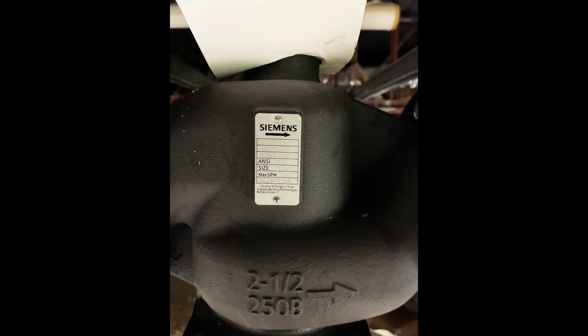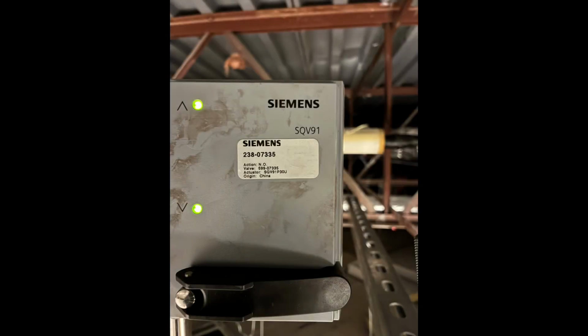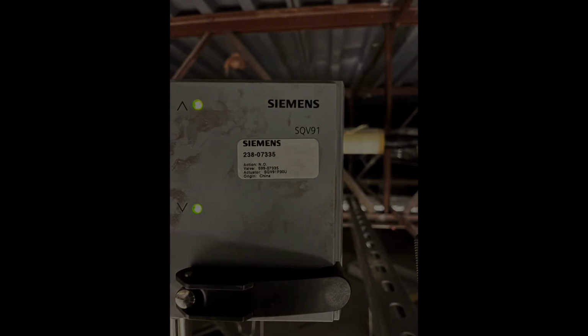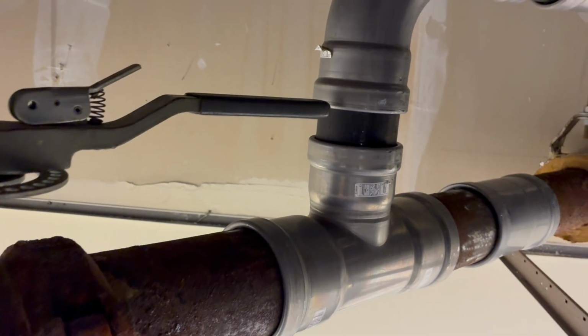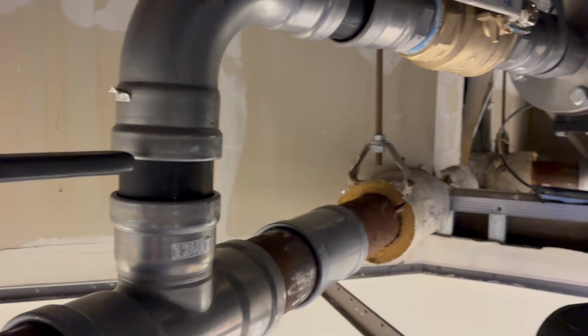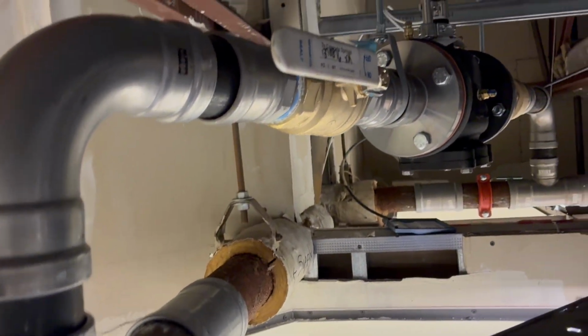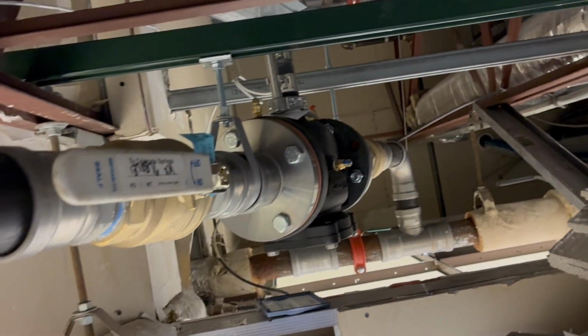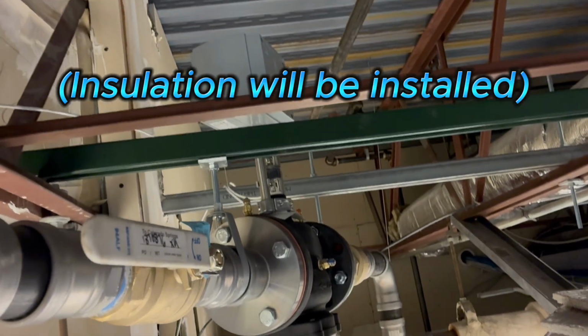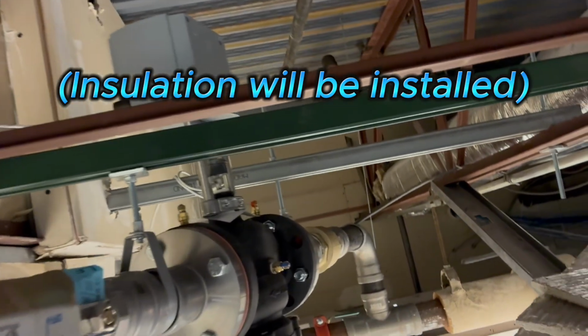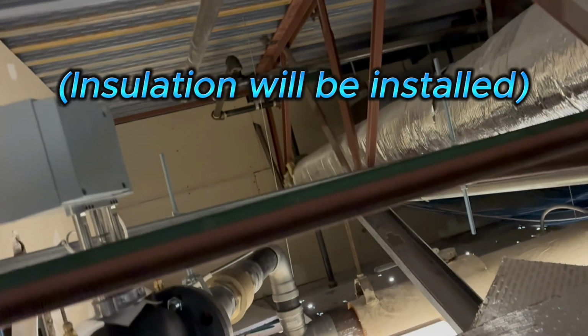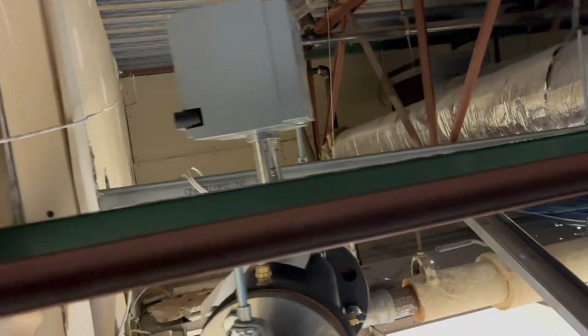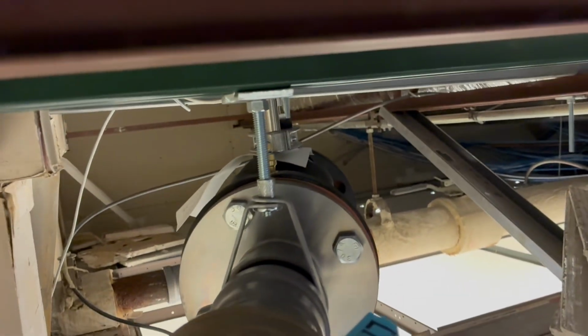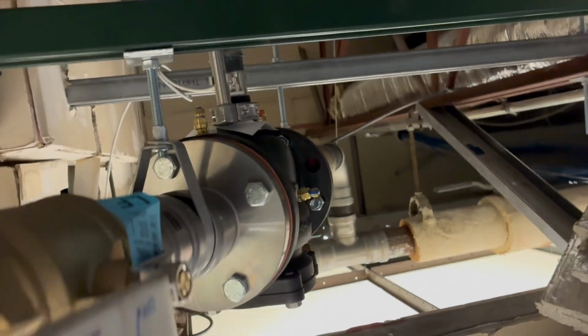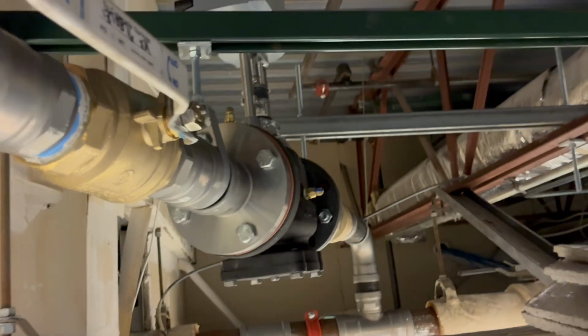Again, also a Siemens product. And these will talk to the BAS. All press fit connections. The HVAC installer did a great job on this install. You also have ball valves on either side of the valve, so if you need to service or replace a valve, you can shut the ball valves. The reason I had to go with the larger diameter bypass loop on the first and second floor was to get the adequate flow rate.